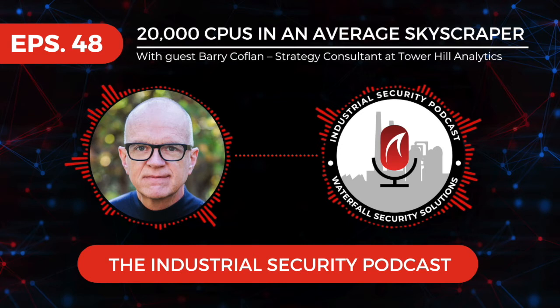So if you want to pick up a remote temperature or a lighting sensor or some device like that, rather than hardwire it to the BMS, they'll bring it up over the internet and push the data back down into the BMS. The protocols in that case are varied. They tend to be IoT protocols like MQTT or other IoT type protocols. They're not necessarily BACnet in that case.